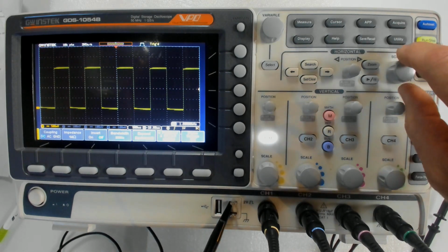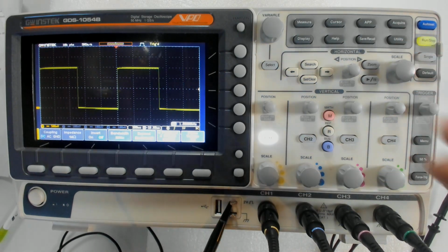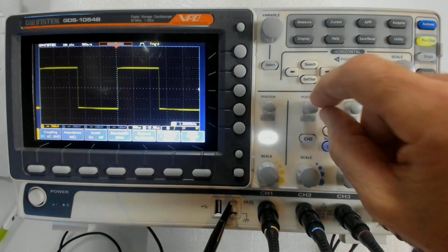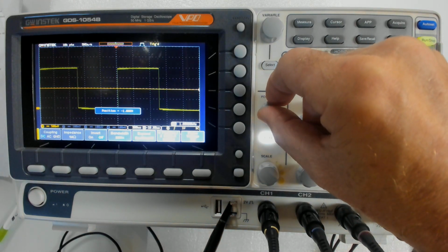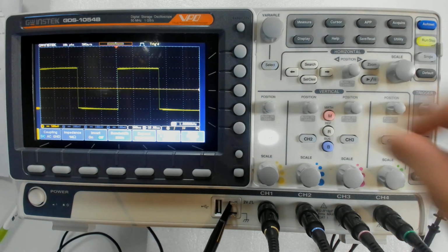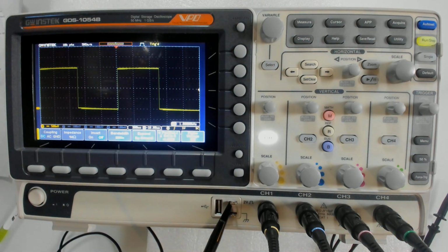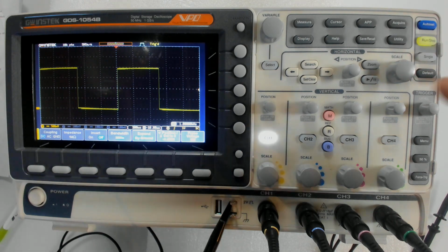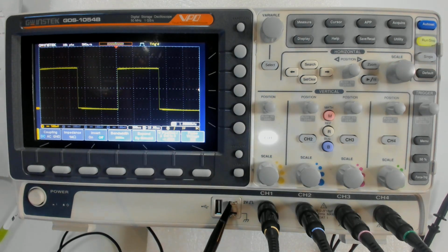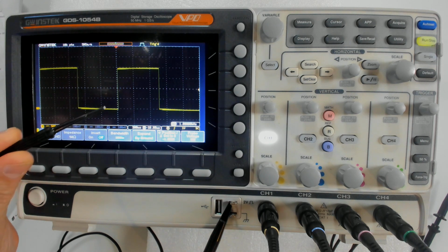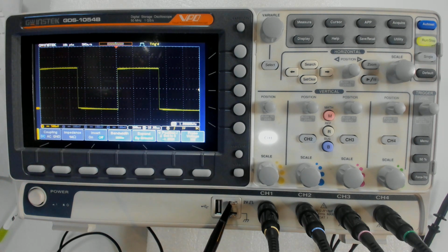You'll hear me say a lot that bigger is better with scopes and with anything. You make it large and then you can see better resolution and see how well you're doing. And it looks like we did pretty good. Even with it blown up to a bigger size, it still looks pretty square. I could maybe adjust it a little bit. But I'm going to do one more thing, and that is there's an averaging function that will probably even clean up the noise. Wherever it's a little bit thick there, that's a little bit of noise coming in.